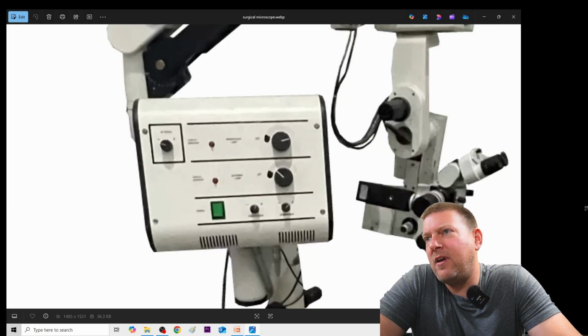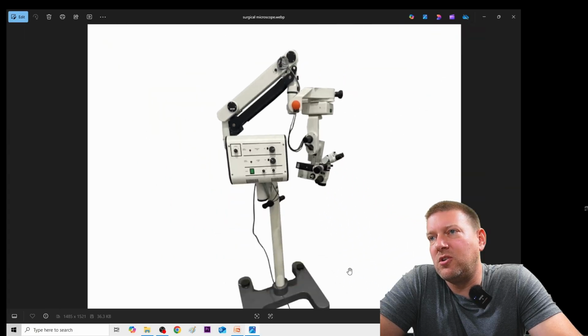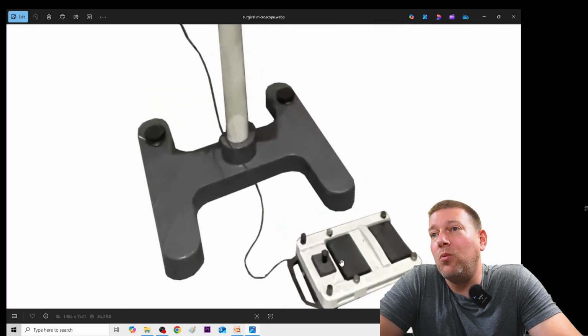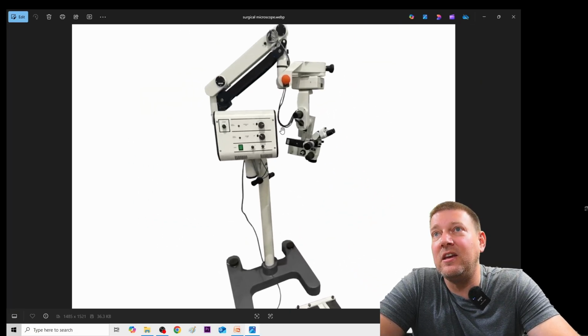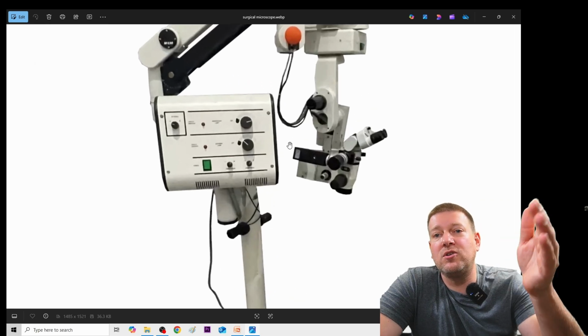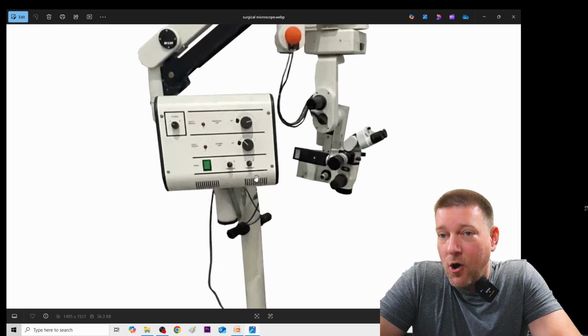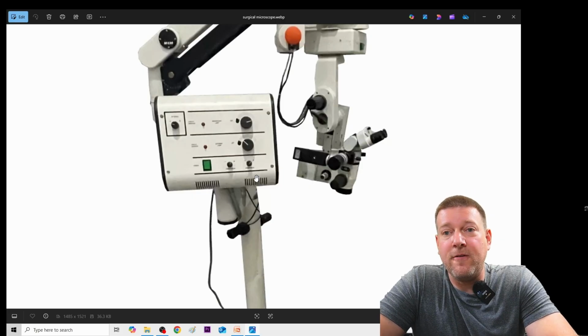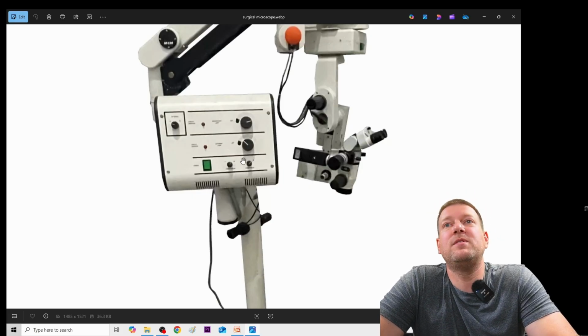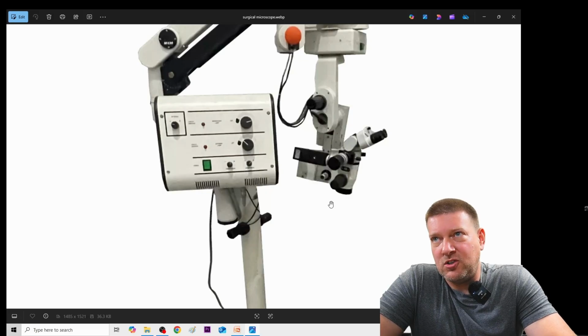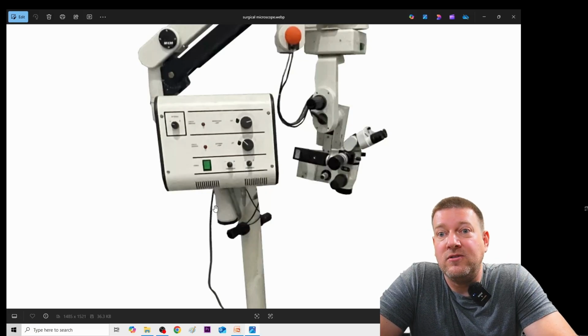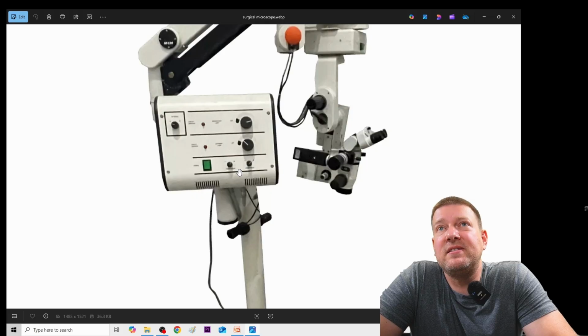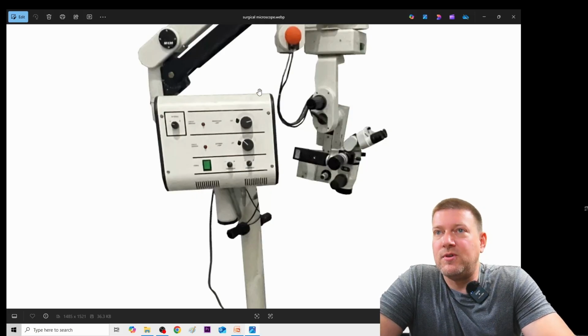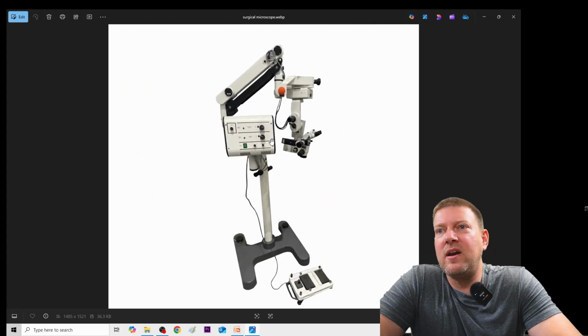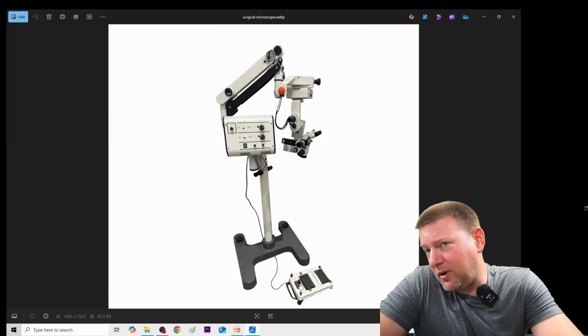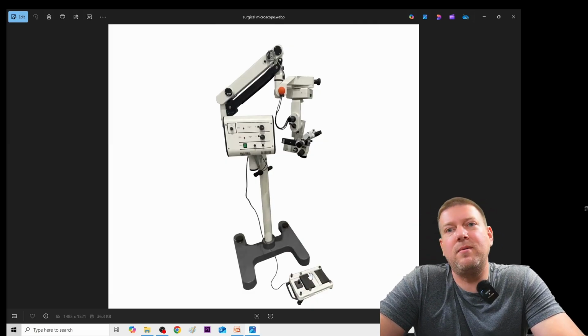What we'll have is a focus mechanism, controlled down here by the foot control, but we can actually do that very easily on a Gen 2 product. All you're going to do is control the motor one way or the other, but if it's got autofocus, any sort of autofocus is going to be Gen 3 to Gen 4. So if it doesn't have autofocus and it's just controlling the focal in and out, the zoom in and out, and even the intensity of the light, that's Gen 2. I'll put that one square in that. This might be a digital controller down here. If it is, Gen 3, but we'll see.